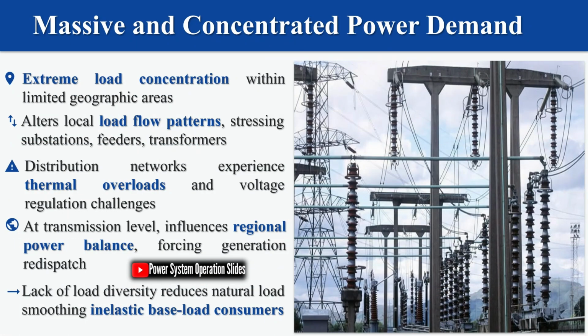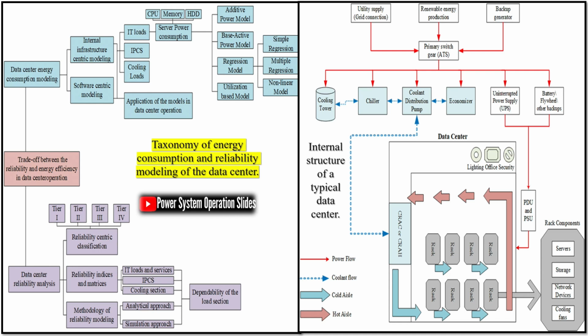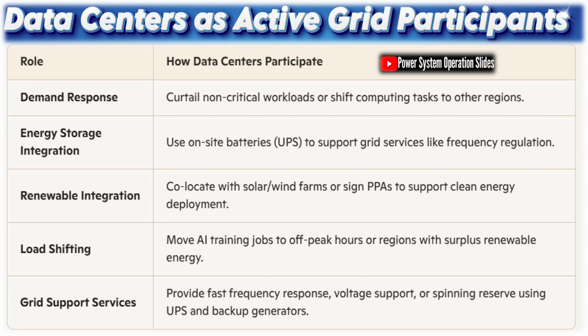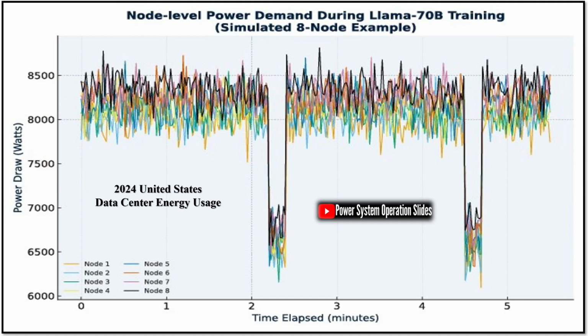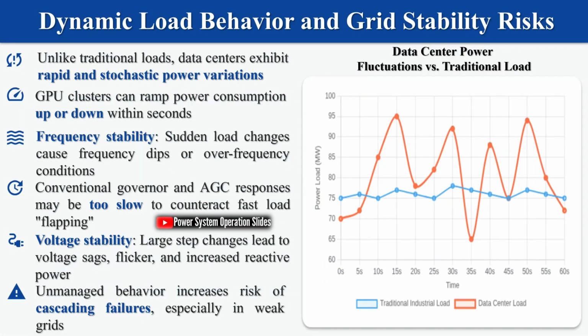The impact of data centers on power system operation is multifaceted and significant. Perhaps the most immediate challenge is their massive and concentrated power demand. Data centers exhibit extreme load concentration within limited geographic areas, with individual hyperscale facilities routinely demanding 50 to 100 megawatts or more, and campus-style developments exceeding several hundred megawatts. This concentration significantly alters local load flow patterns, stressing substations, feeders, transformers, and transmission corridors. Distribution networks originally designed for diversified, low-density loads may experience thermal overloads and voltage regulation challenges. At the transmission level, large data centers can influence regional power balance, forcing redispatch of generation and congestion management actions.